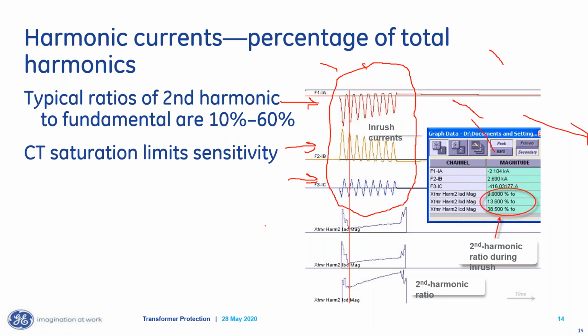Okay, and that second harmonic content can be used to block the differential element when we energize the transformer. Now, the way that this was traditionally done back in the electromechanical relay days is they built a filter. Filter was tuned to 120 hertz. That filter basically provided opening torque to a coil. So it would keep the coil open.